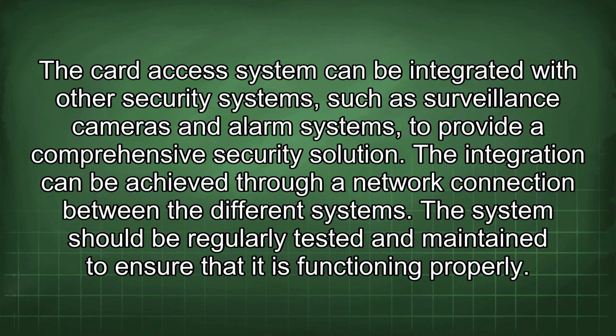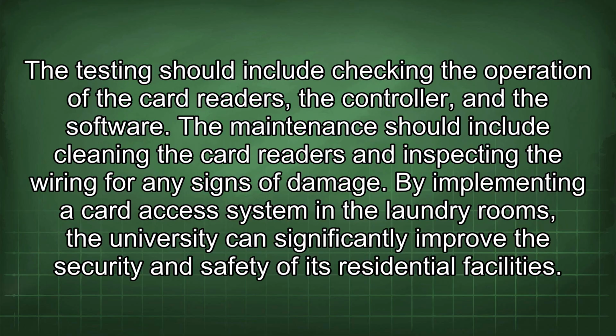The card access system can be integrated with other security systems, such as surveillance cameras and alarm systems, to provide a comprehensive security solution. The integration can be achieved through a network connection between the different systems. The system should be regularly tested and maintained to ensure that it is functioning properly. The testing should include checking the operation of the card readers, the controller, and the software. The maintenance should include cleaning the card readers and inspecting the wiring for any signs of damage.